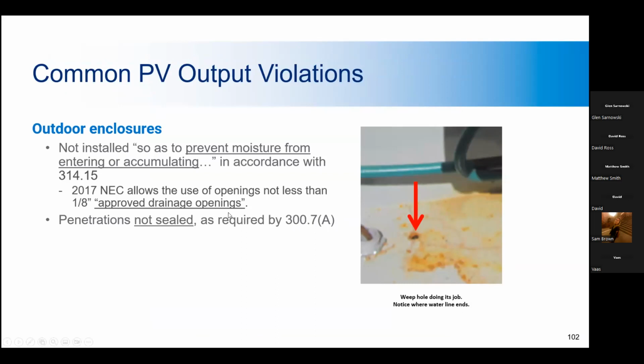Outdoor enclosures may need what's called a weep hole installed. This is an effective way to allow water to exit an enclosure to avoid pooling. Weep holes are used to prevent moisture from accumulating in the enclosure. You can see here the water line kind of ends right where that weep hole is, showing that it did effectively drain the system. These obviously should not be sealed, as they're specifically there to let water leave the box. So if you see a hole like that in an enclosure, it's not a violation. It's part of how they allow drainage to happen.